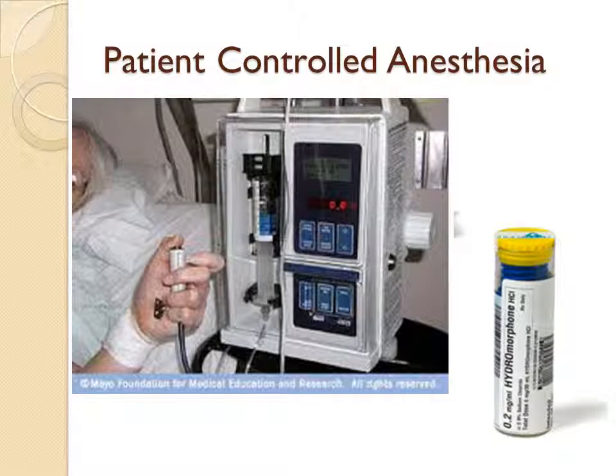You provide the client with a PCA button, and then you provide them with the PCA education. The PCA pump is set according to what the doctor orders. The medication can infuse continuously. It can infuse continuously and have bolus doses administered by the client when they push the button. Or medication may be administered in bolus doses only when the client pushes the button. The pump is programmed to provide a certain medication dose at prescribed intervals with a prescribed 4-hour lockout dosage.